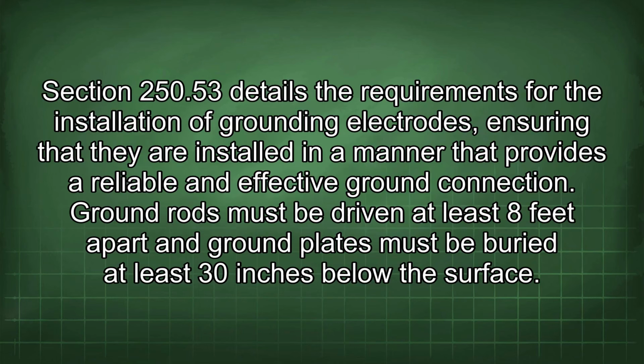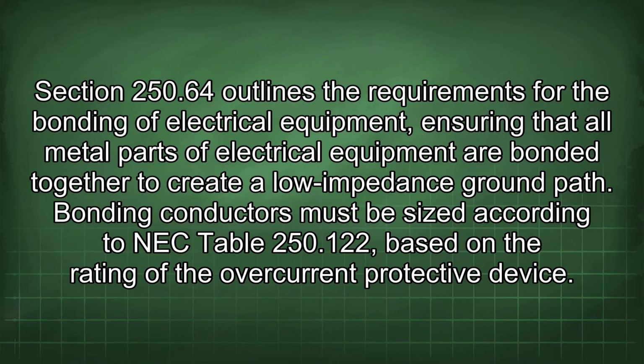Section 250.53 details the requirements for the installation of grounding electrodes, ensuring that they are installed in a manner that provides a reliable and effective ground connection. Ground rods must be driven at least 8 feet apart and ground plates must be buried at least 30 inches below the surface.